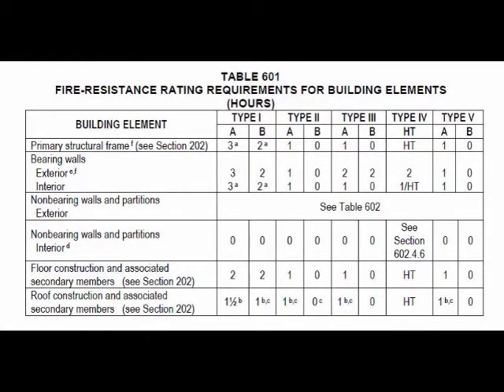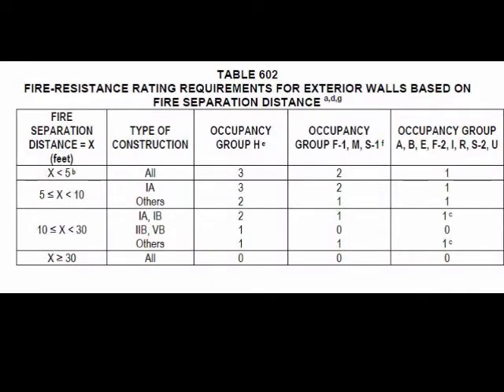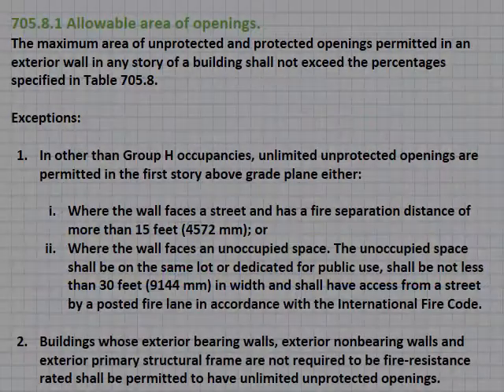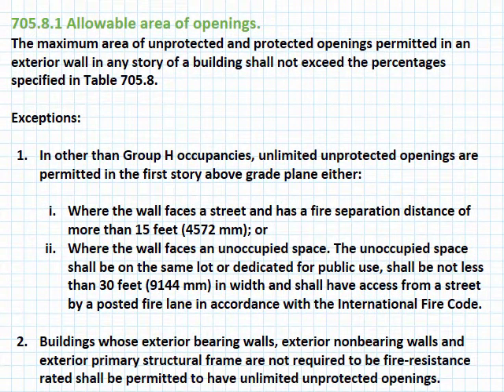IBC Table 601 specifies the minimum fire resistance rating requirements for primary structural frames, and Table 602 specifies the minimum fire resistance rating requirements for non-bearing exterior walls based on fire separation distance. For a fire separation distance of at least 10 feet but not more than 30 feet for a Group S1 occupancy, the fire resistance rating of the exterior walls is 1 hour for Type 3B construction, labeled as 'Others' in the second column. IBC Section 705.8.1 Exception 2 is therefore not applicable, and Table 705.8 needs to be consulted.